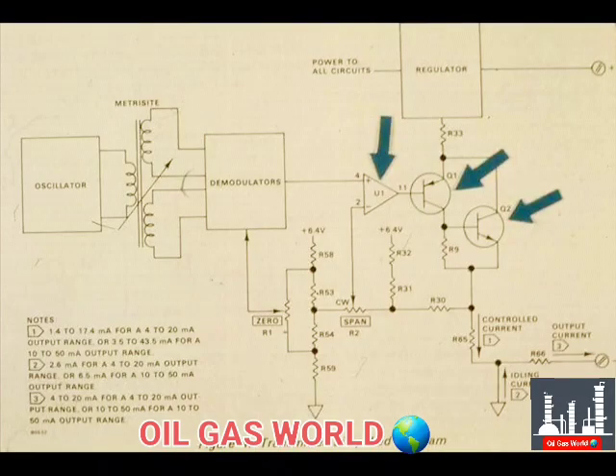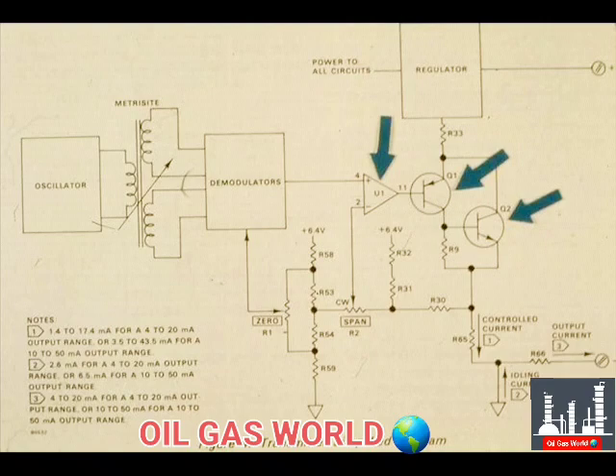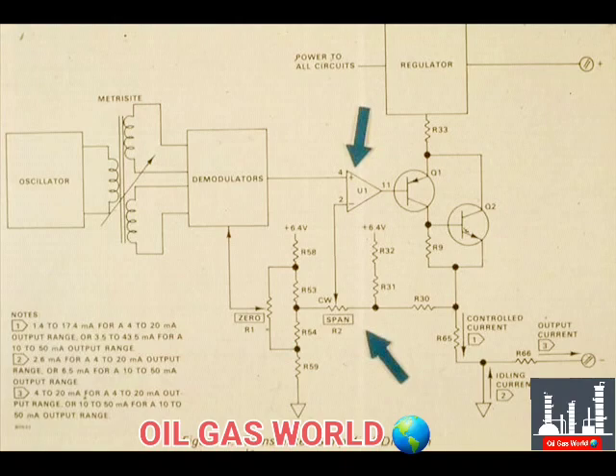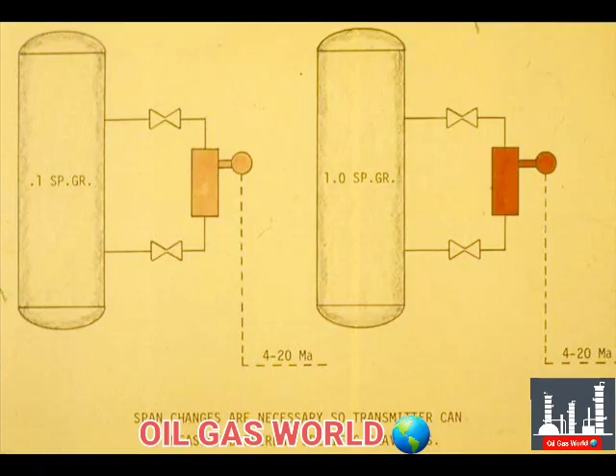This is a simplified schematic of the transmitter. U1, the differential amplifier, biases Q1 and Q2 to control the amount of current through the transmitter. The transmitter output current passes through Q1 and Q2. The span potentiometer adjusts the amount of feedback that goes to the differential amplifier. Varying the feedback varies the gain of U1 amplifier and ultimately the gain of the transmitter. Span changes are necessary so the transmitter can measure different specific gravity fluids.